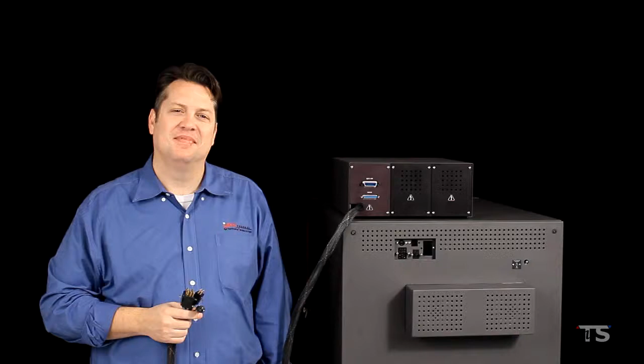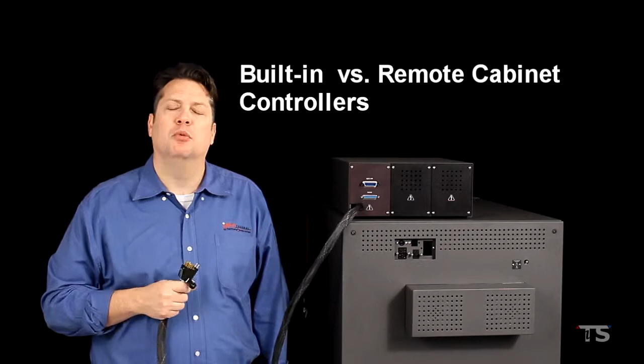Now we are ready to connect our controller to the chamber. Your thermal chamber's controller may be built into the chamber or installed in a remote cabinet. If your controller is built into the chamber, you don't have to make any connections. If your controller is in a remote cabinet, this video lesson will show you how to make the connections between your remote C4 and your thermal chamber.